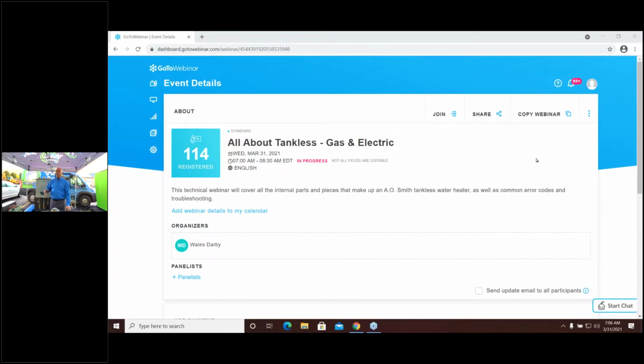So there's about 9.2 million tank style units shipped every year. Okay, out of that, 20% go into new homes, 80% are replacement units, 30% are complete failures, and about 27 million water heaters are over 10 years old. And that's kind of the target number for a tank style water heater, is 10 years.